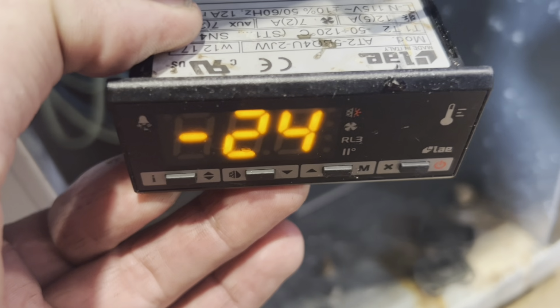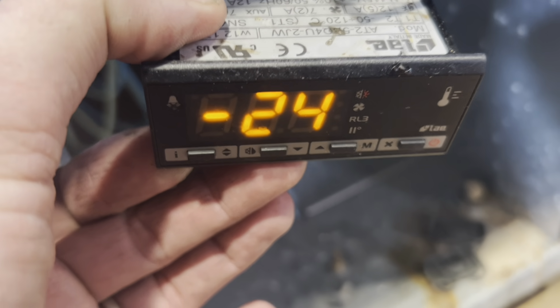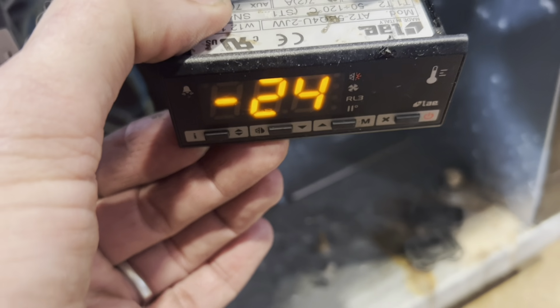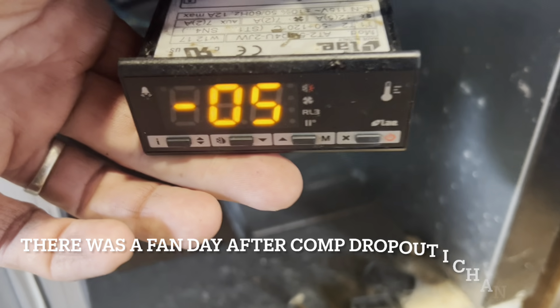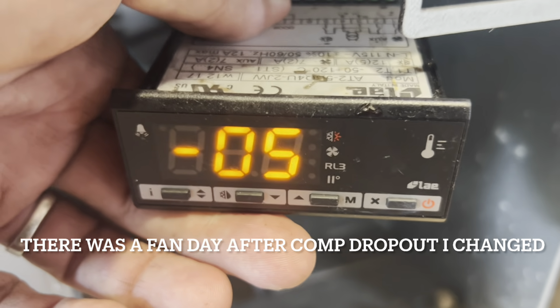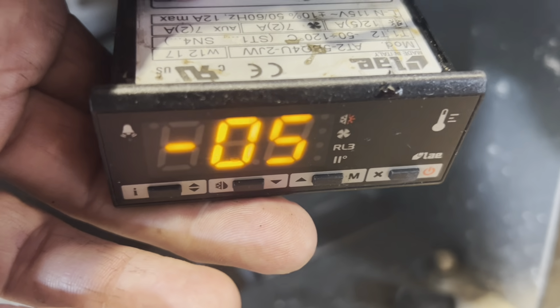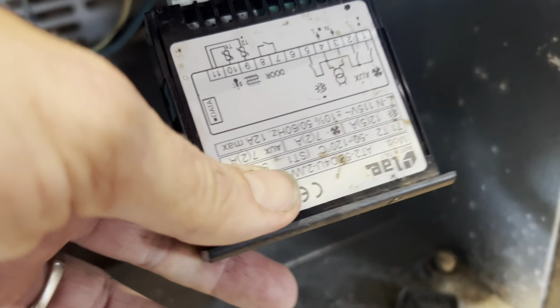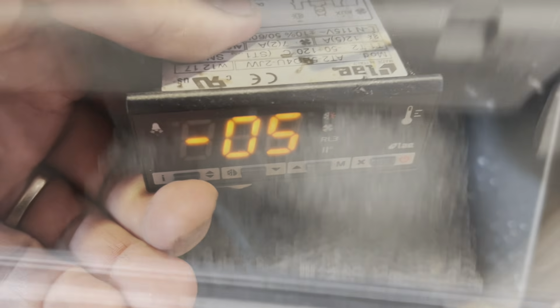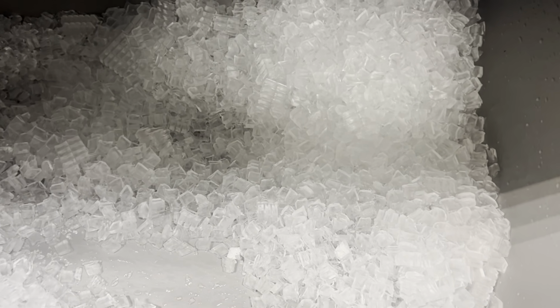Alright, so I reversed the temperature probes on this one too. So that's what our coil temp is reading, so that's good. Something's wrong with the setup because it shouldn't have dropped out the fans. We're not in a defrost and the fan stopped. So what's going on here? Also, they're telling me they got no ice being made, which is correct.